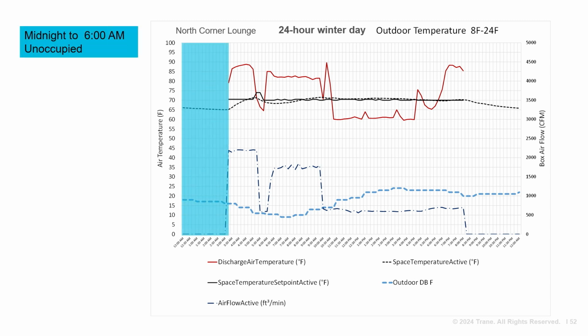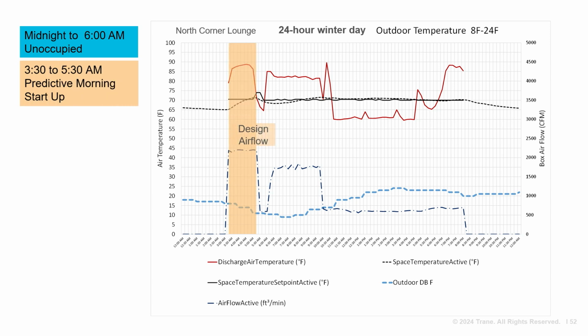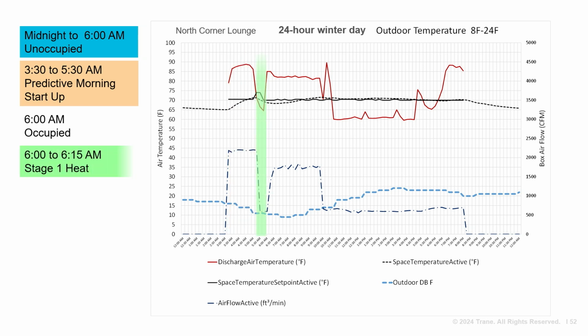During unoccupied hours, the temperature in the space was allowed to drift to 65 degrees. But then the predictive morning warm-up starts, and the air valve and hot water valve are fully open. This raises the room temperature from 65 degrees to 70 degrees. The occupied period of the day then starts with the VAV box at stage 1 heat, air valve at minimum flow, and the valve modulating.